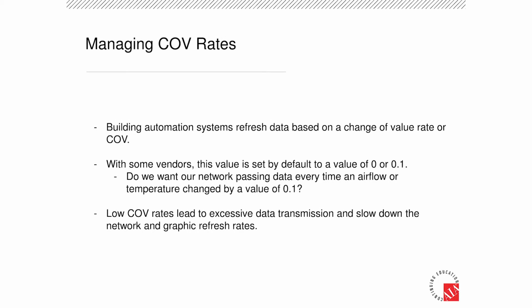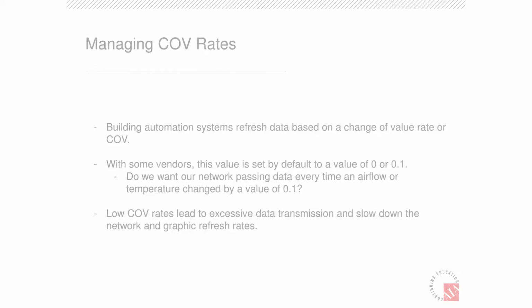Building automation systems refresh based on COV rate for the most part, and COV is change of value. I learned this the hard way on a project when I was installing it. We had a couple hundred VAV boxes on a very small network, and the network kept crashing. I got on the phone with tech support, and they asked, what's your COV rate? I had never heard the term before, and by default, the equipment vendor I was working for had COV rates out of the box set at either 0 or 0.1, meaning anytime any analog value changes by 0.1, it sends information back across the network.